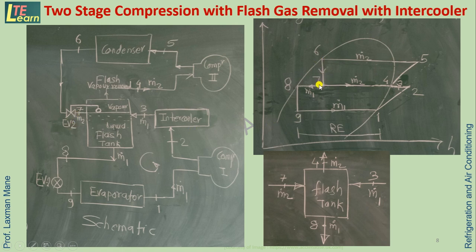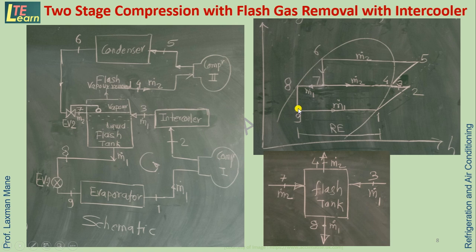From 6 to 7, upper expansion takes place through expansion valve 2. At point 7, liquid is separated from flash vapor in the flash tank — the saturated liquid (7 to 8) is passed through the lower expansion valve, giving expansion from 8 to 9 on the PH diagram. Across the evaporator, enthalpy changes from point 9 to point 1.